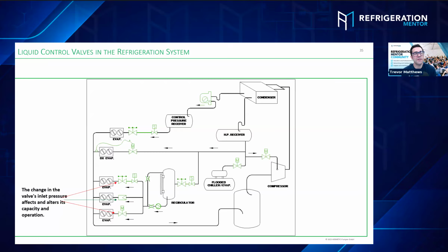So, because you set it up for that specific flow of the pump, and now all of a sudden the pump doesn't have that flow because we dropped the flow because of a drive, and now we're not getting the same amount of flow through that coil, because it's a hand expansion valve example. Exactly. We're going to maintain the 40 psi differential, meaning you have a constant pressure on the pump discharge going direct to your valves.